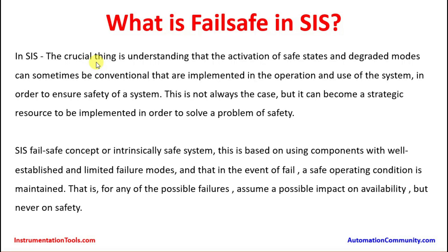The crucial thing is understanding that the activation of safe states and degraded modes can sometimes be conventional, implemented in the operation and use of the system to ensure safety. This is not always the case but can become a strategic resource to solve a safety problem. The safe state — whether the valve goes to closed or open — must be decided according to the process and engineering requirements.